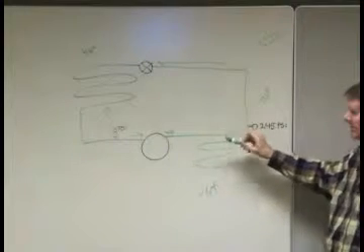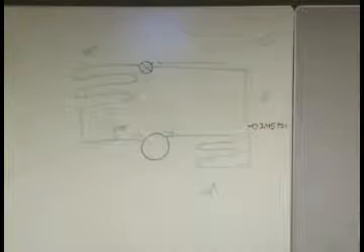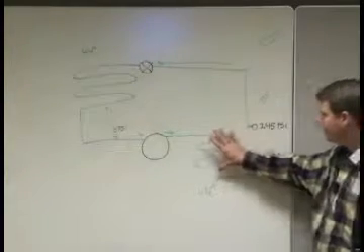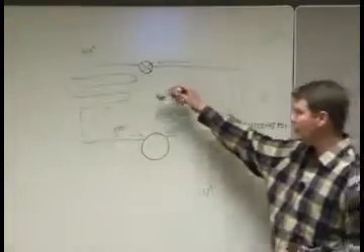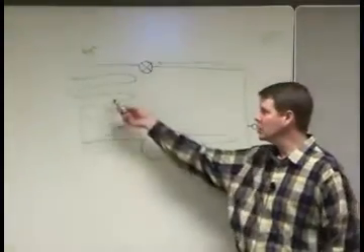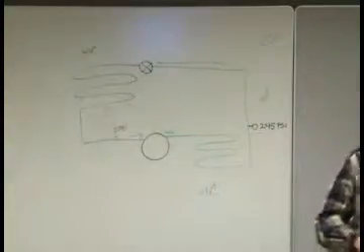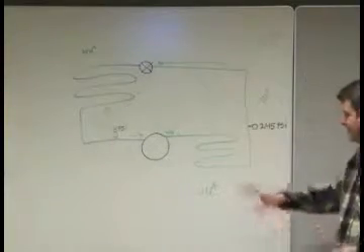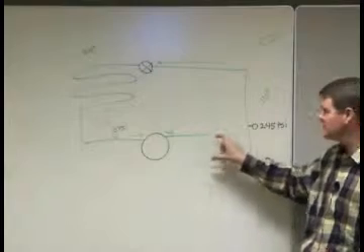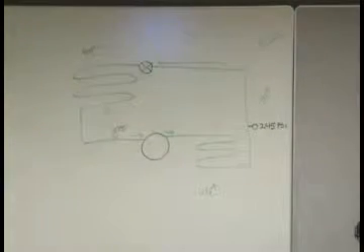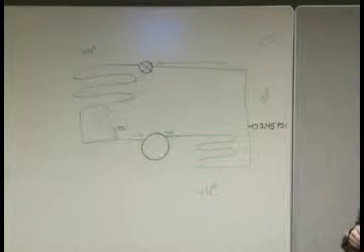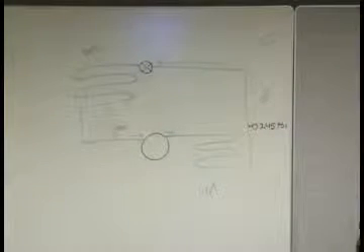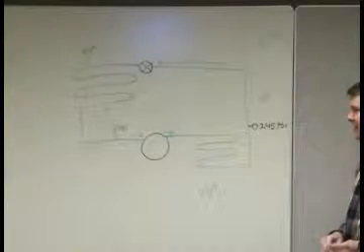There's water cooled, where this condenser coil is cooled by some water source, like a well. They can both be water coils, where we're cooling water or glycol, and that would be a chiller. But we're doing the same things here. They size the coils and design them around these pressures and temperatures that we ultimately want to achieve. So they can do a lot of different things.